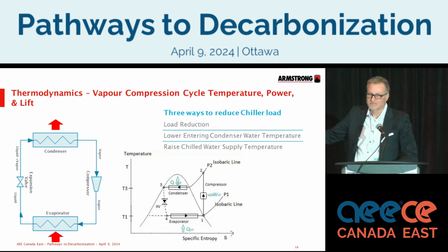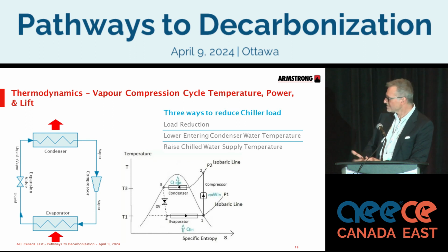And then lastly, the refrigeration cycle. Simply put, there are 3 ways to reduce chiller load in a simple form: load reduction, lowering the entering condenser water temperature, or raising the chilled water temperature set point. If you look at the graph, when you lower the condenser water temperature or raise the evaporator temperature, all you're doing is lightening the load on the compressor, and the compressor has to do less lift. That's the process here. So understanding those fundamentals, first and foremost, is key when you start talking about what optimization is all about.